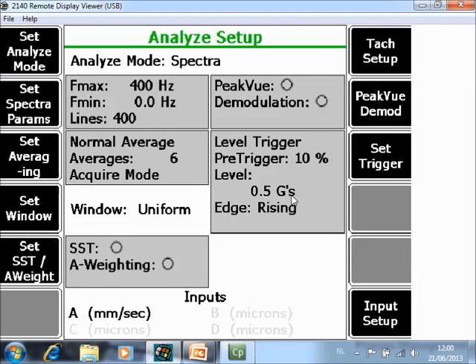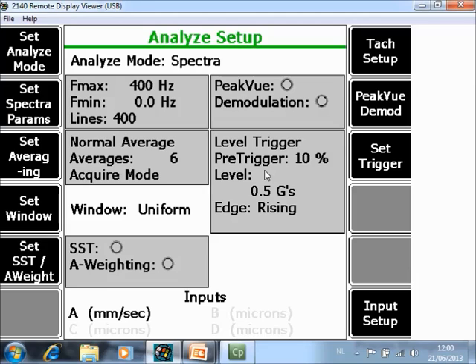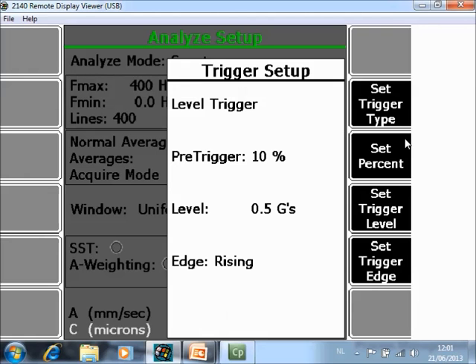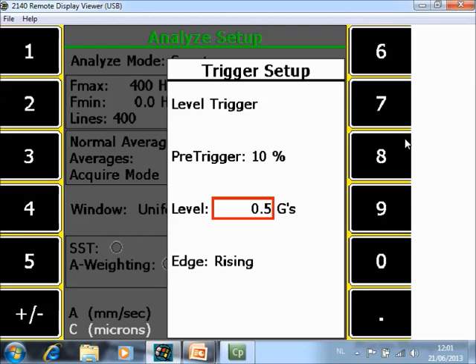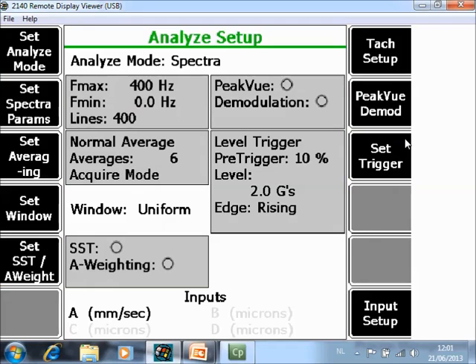Now the two problems that may occur here are if there are already a lot of background vibration in the neighborhood or on the installation. Maybe the background vibration is already higher than 0.5 G's and then the CSI 2140 will start collecting data without your impacts and then you don't have good data. If that is the case, you can simply make this number higher. Go to F9 set trigger, go to F10 and for example change it to 2 G's. Now only vibration levels higher than 2 G's will be considered as vibration coming from your impacts.